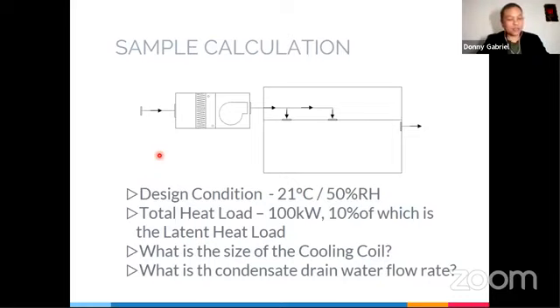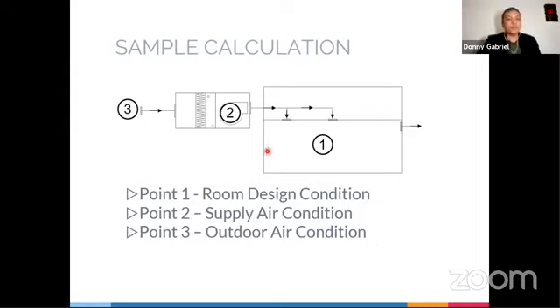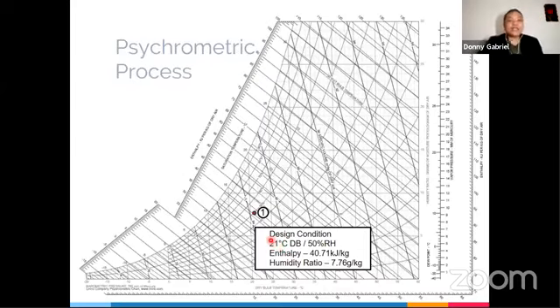All right, so we will try to calculate. We will try to check. First, define our points. Point 1, this is our room, so we will define our room condition. Point 2, our supply air condition. So what is the condition of the air supplying to the room? And 3, if it's coming from outside, what is the outdoor air condition? In our previous example, we say the design is 21 degrees C, 50% RH. So how did we get this point?